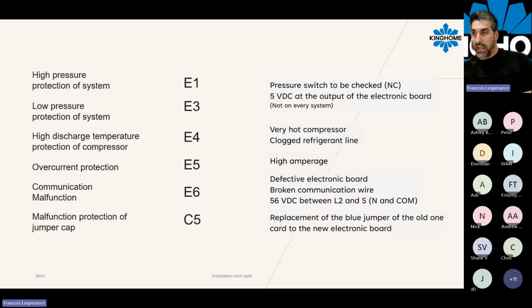C5 is a problem that appears when you do a replacement of an electronic board. You have a blue jumper cap that you need to keep from the old board and reinstall into the new board. When we order parts from the factory, like the control board for a system, they will send it out blank. So it needs to have this jumper cap to make the identification of what is the system. So you need to keep the old blue jumper from the previous board and put it on the new board. If you forget to do it, you will have a C5 error right when you start the unit.